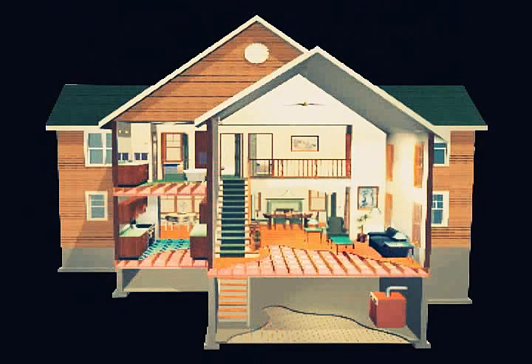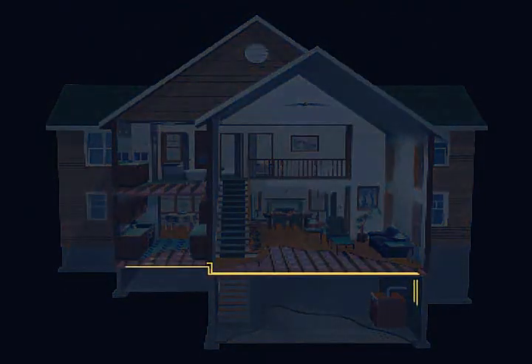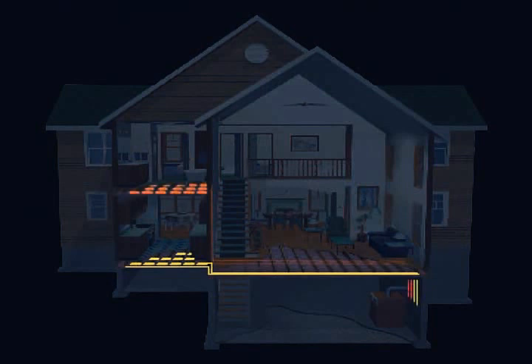For maximum efficiency and total comfort, every room of the house should have its own separate tubing circuit connected to the boiler manifold with its own dedicated zone valve, which in turn is connected to its own individual thermostat control. These separate circuits with their own thermostats we call comfort zones.